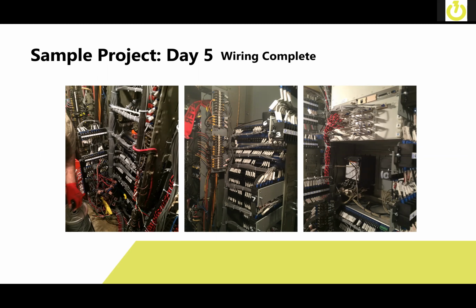Because we came in, we had a full add delete list that we were able to work off of. So while we're doing the demolition, we're not looking at any drawings whatsoever, unless there is a major issue with what we expected to find. You can see new terminal blocks have been installed, all the wiring's been installed and tie wrapped in place, and wire labels and everything have been installed too.